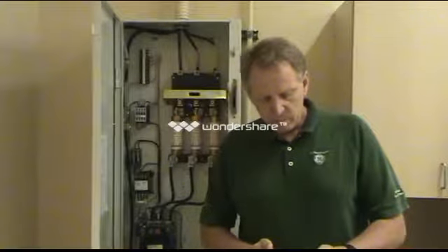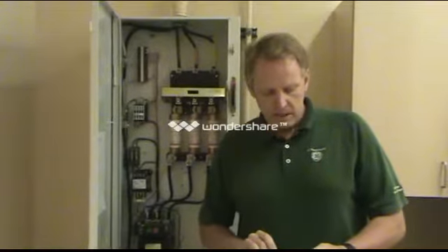Pretty much your system ID, your GON, your address, site name, etc. A couple of things to think about here. It's going to ask you for your modality and system model type. What's not written on these forms is if you have an X-ray system, you're also going to want to know what the kW rating of the generator is. So make sure and note that down.